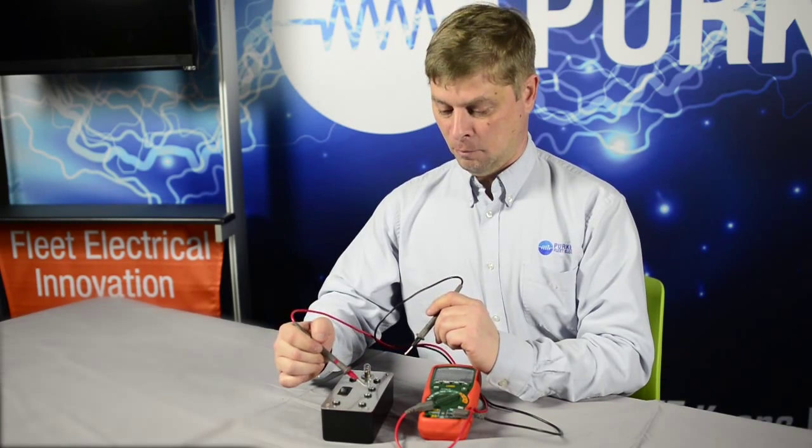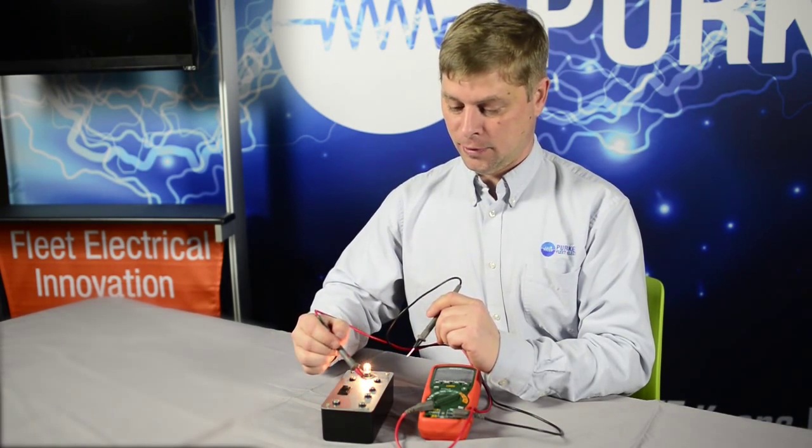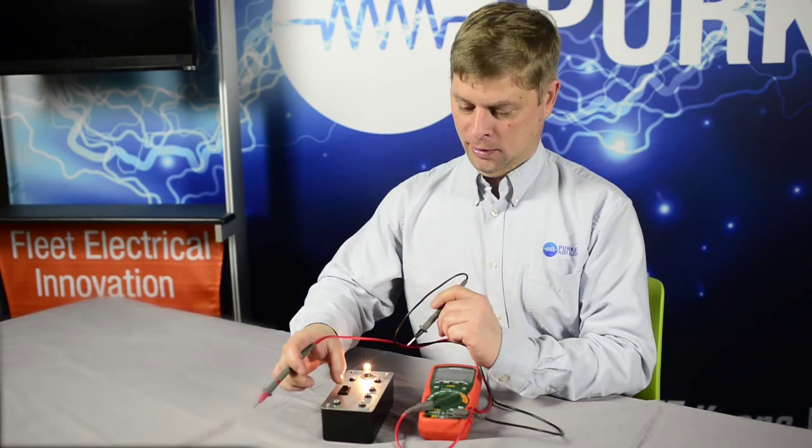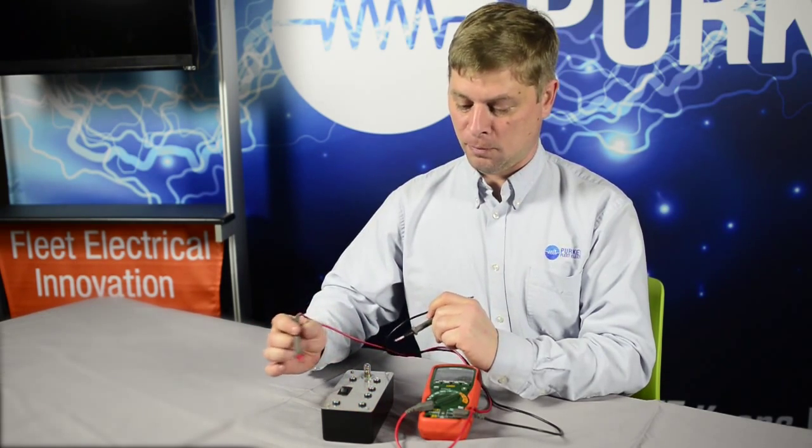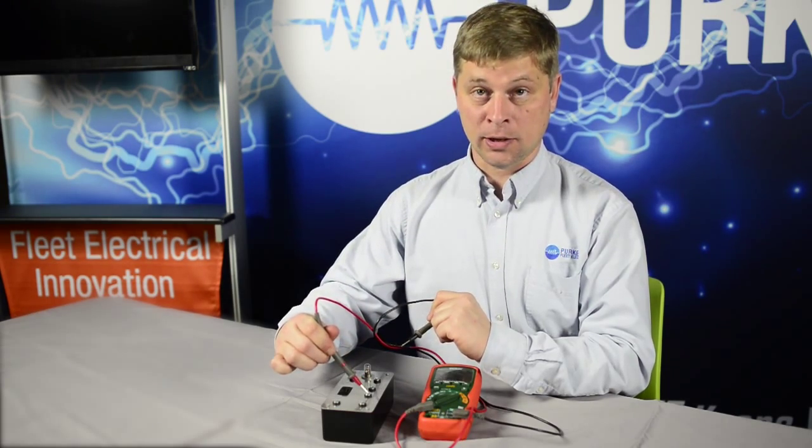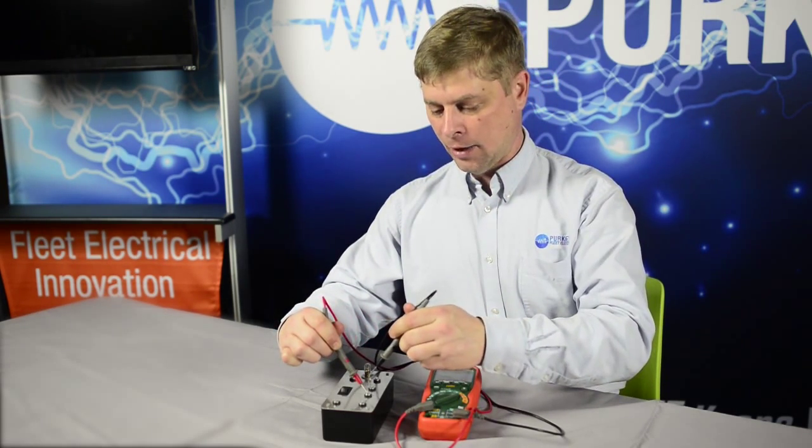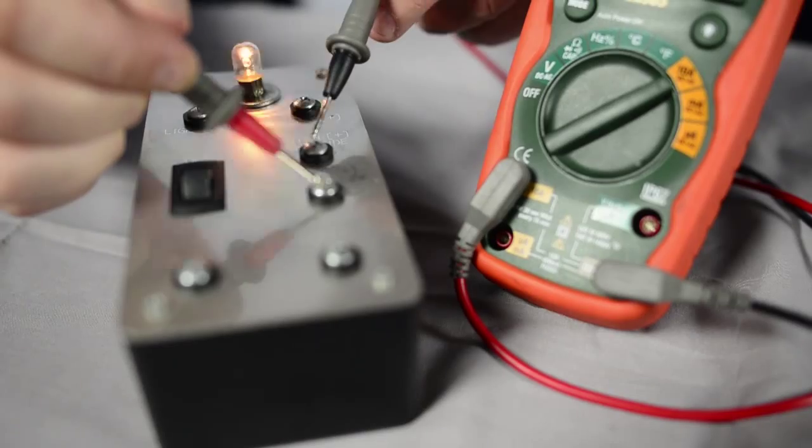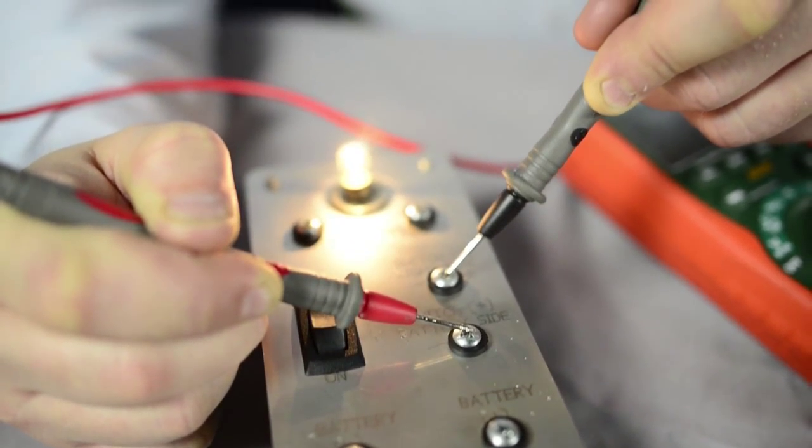The way this works is, before we used our switch to connect this point to this point. Now, instead of using the switch, we're going to use our meter. Go on one side of the switch, it's going to flow through the red lead, through the meter, come back out of the black lead, and complete the circuit. That way, all the current is flowing through our meter.